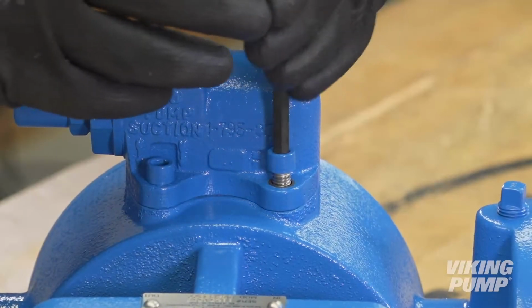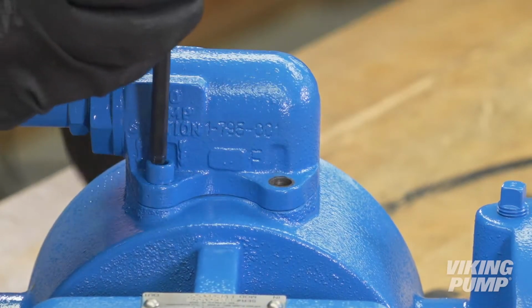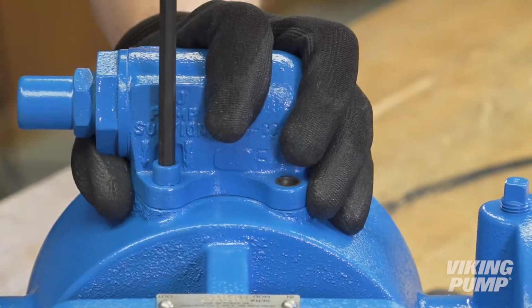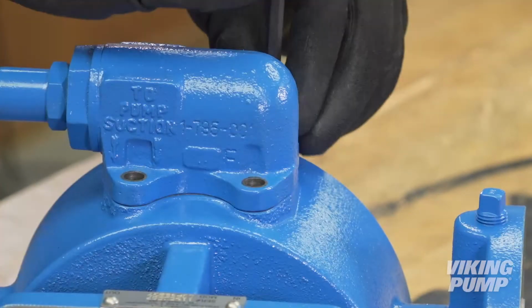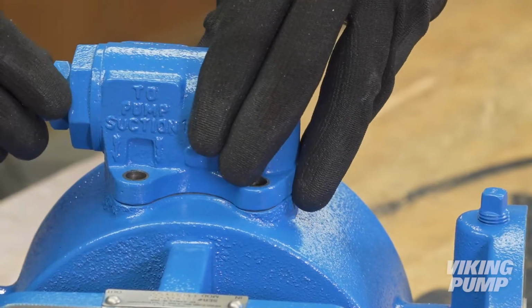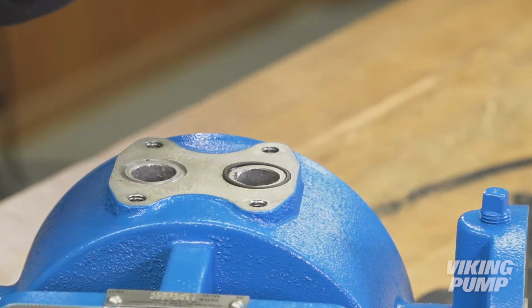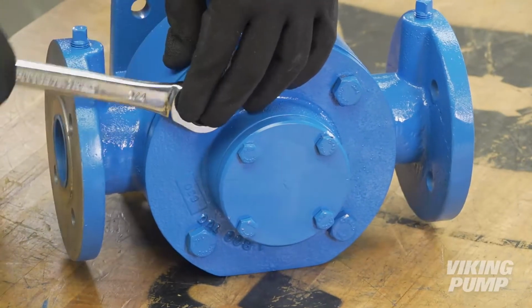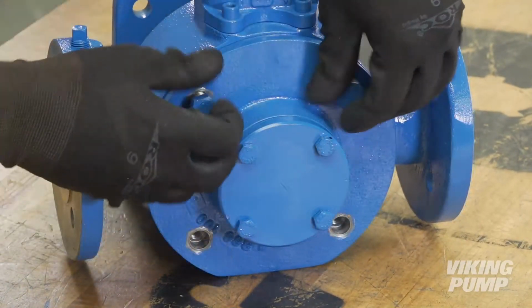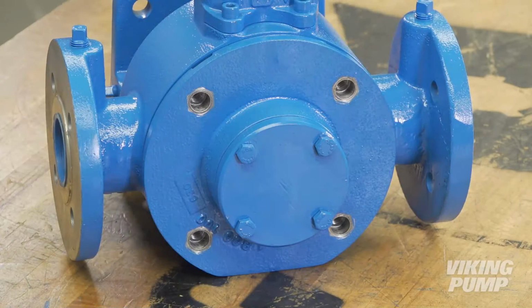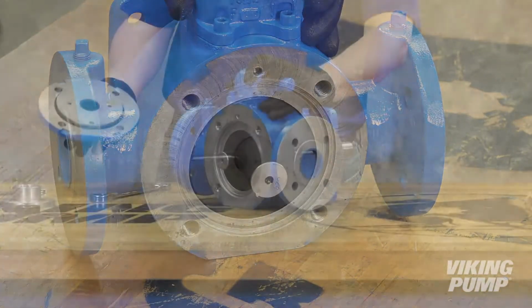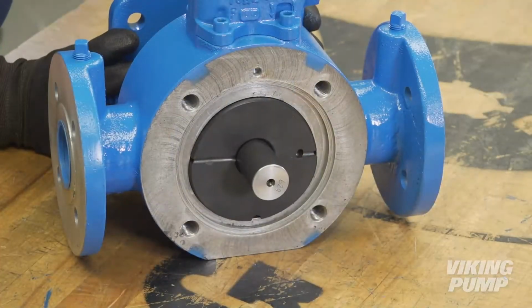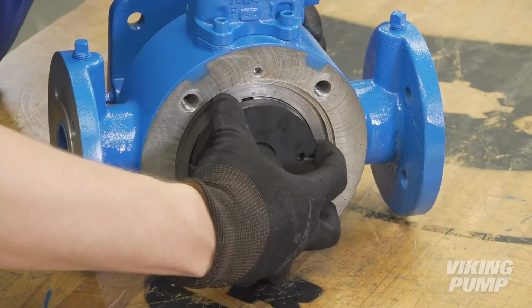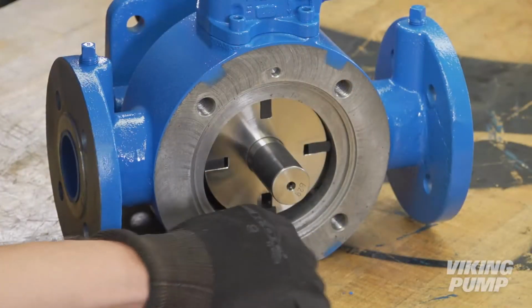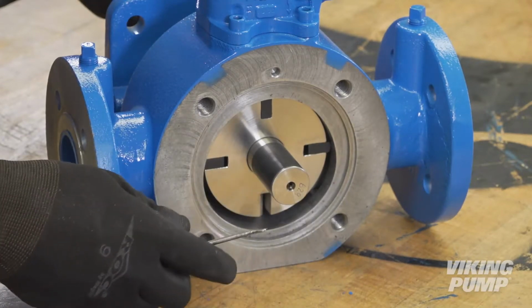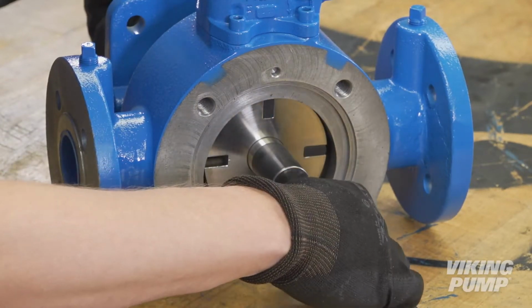It is not necessary to remove the relief valve from the pump casing, but if removing the relief valve, take note of the orientation to ensure the valve is properly oriented when reinstalled. Marking the valve and pump can help ensure this. First, loosen and remove the head bolts. Remove the pump head and discard the head O-ring. Remove and discard the first carbon disc. Remove and discard the vanes from the rotor slots. Rotate the shaft by hand to remove each vane.